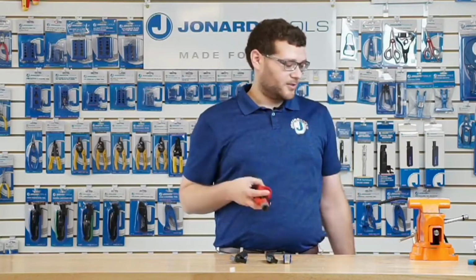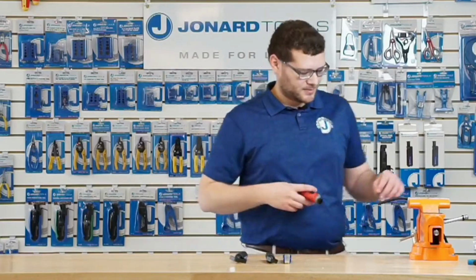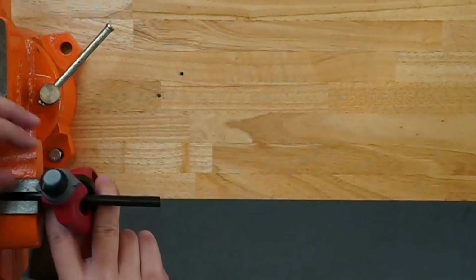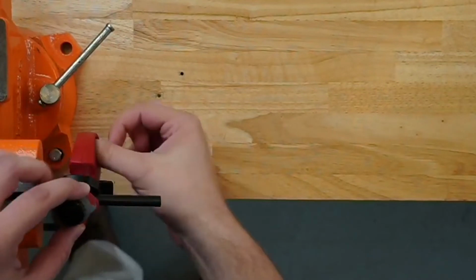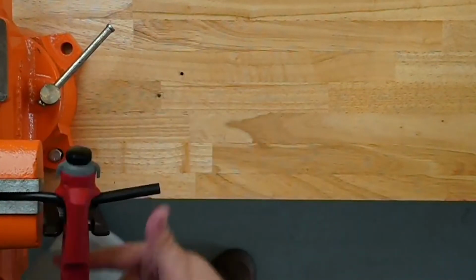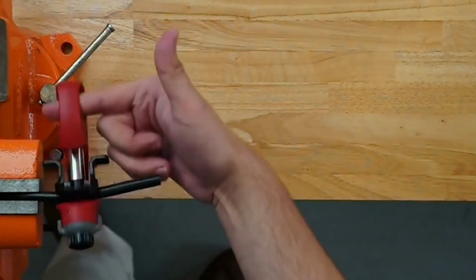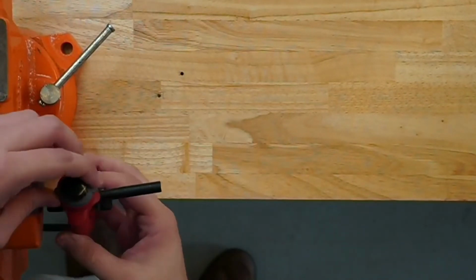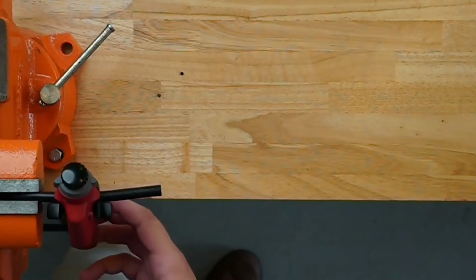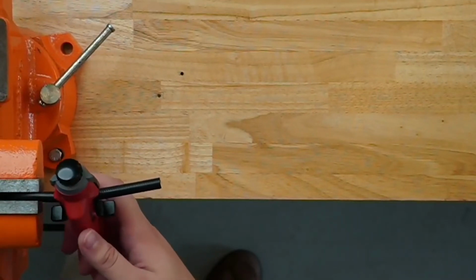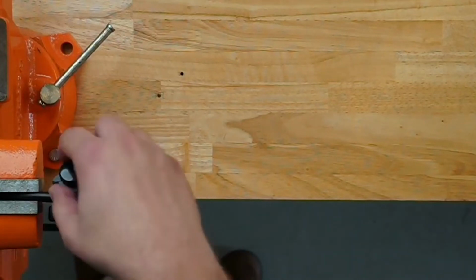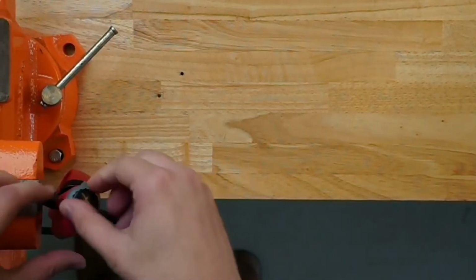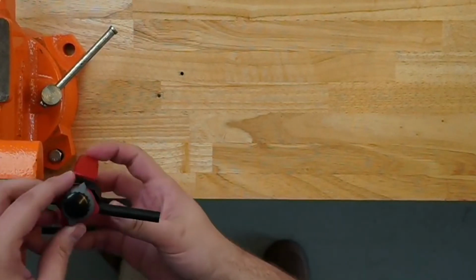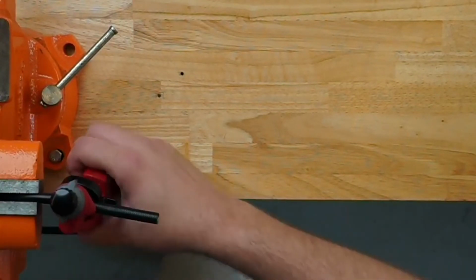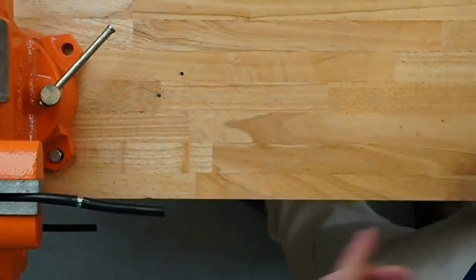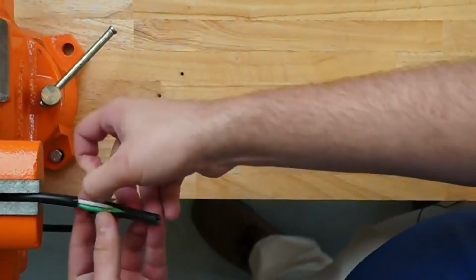So I'll just show you how to slit and ring using this tool. By the way, all of these blades have been preset just to make this demonstration a little easier. When you're working on cables in the field, you're going to want to test the slit and ring tools on a junk piece of cable just to make sure that the blade is set in the correct position. So once we're done ringing, you simply rotate the collar to the slitting position and you pull it towards you like so, and the cable jacket is slit.